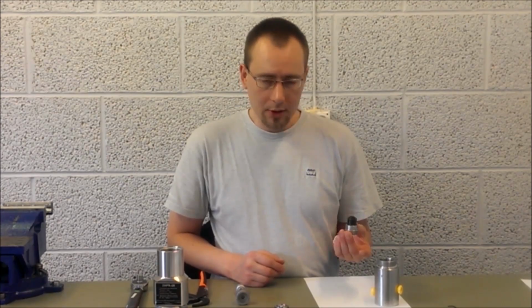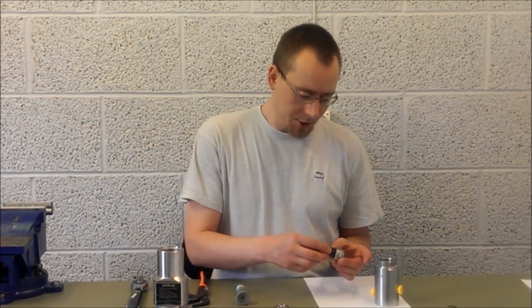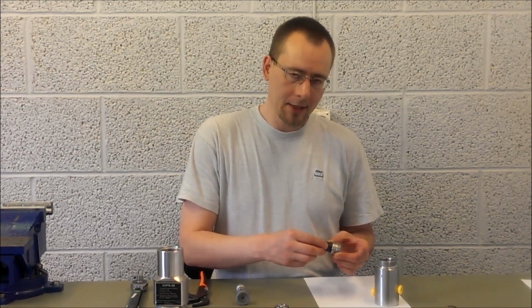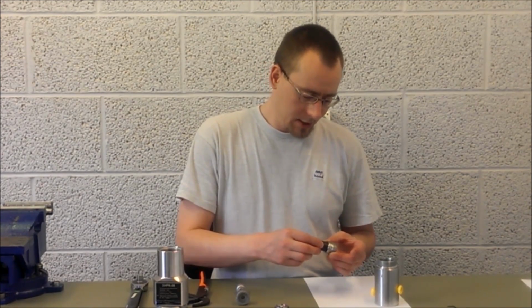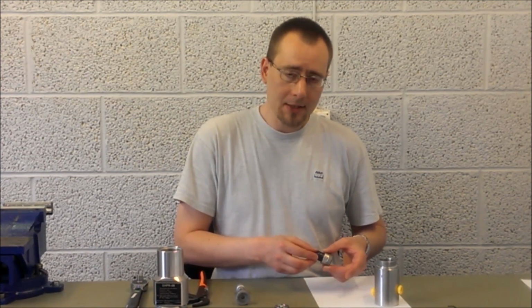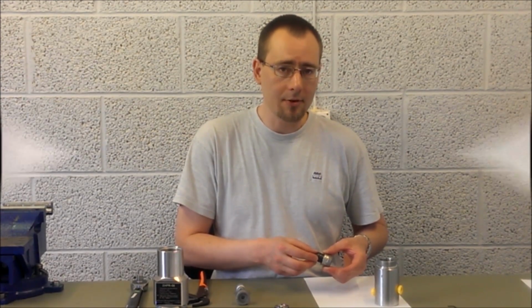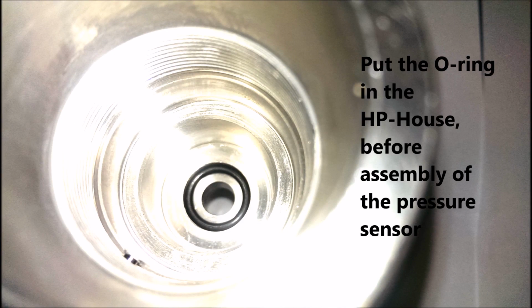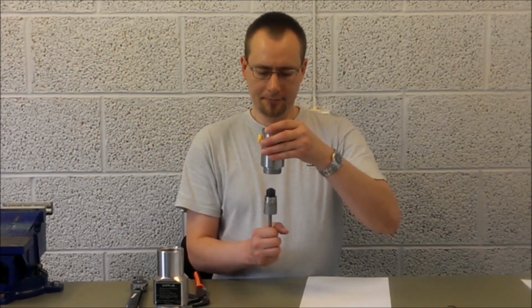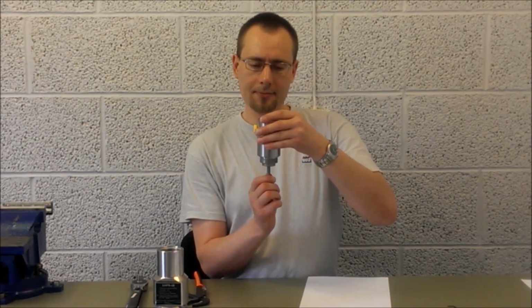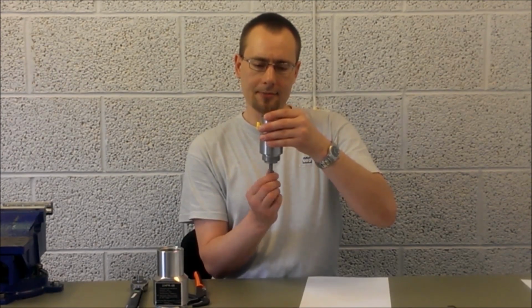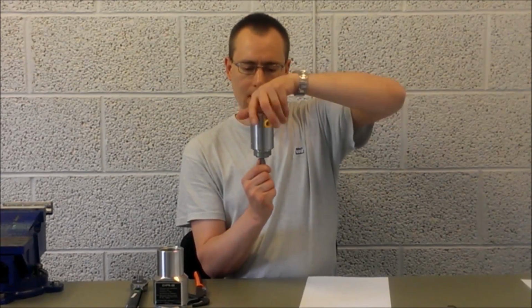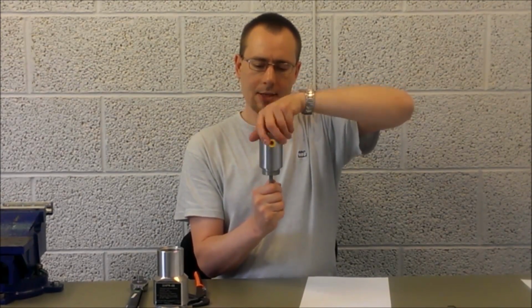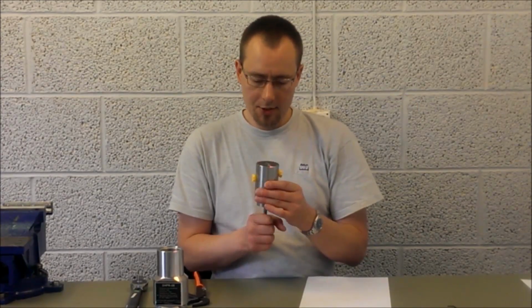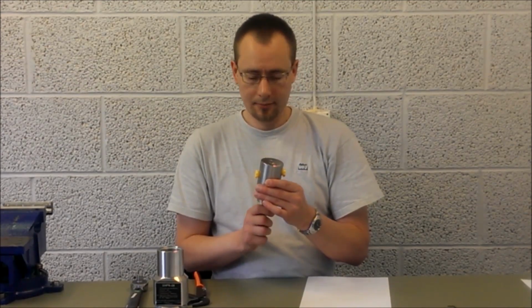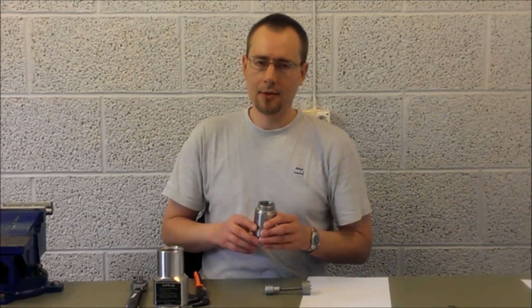Take a test, hold the guide sleeves together and push the sensor element to feel the spring in the dump valve. When you can feel the spring, it means the calibration bolt has been assembled correctly. Hold the housing like this and guide the pressure sensor inside the housing and find the threads. When you got the threads, turning of the housing is an easy way. When you have reached the bottom of the housing, fixate it and put correct torque.